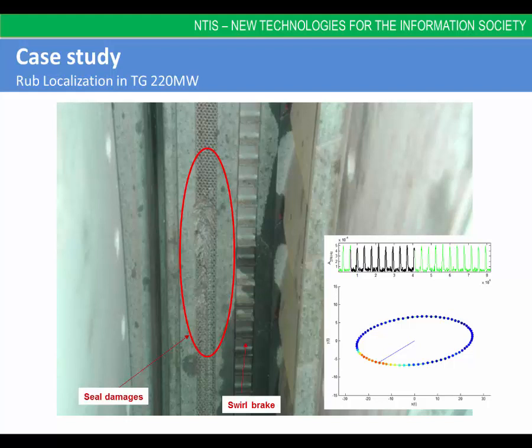In the right bottom picture the result of tangential localization for blade contact is shown. The upper part shows the waveform of average amplitudes versus time. At the bottom, the filtered first harmonic orbit corresponding to the signal of shaft vibration is displayed. The amplitude of the characteristic frequencies is scaled in colors where blue corresponds to the minimum amplitude and red is the maximum value. From this representation it is evident when the highest intensity of contact between the rotor and stator occurs, and it is only a matter of processing to automatically evaluate the angle of maximum rubbing intensity.